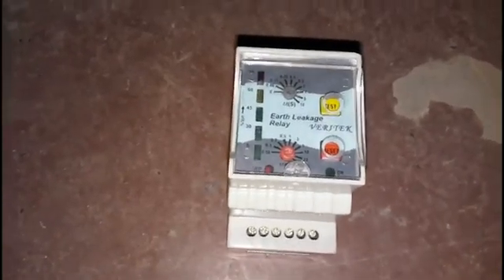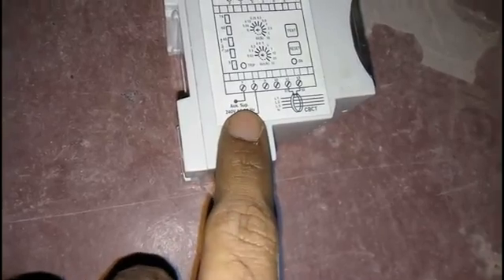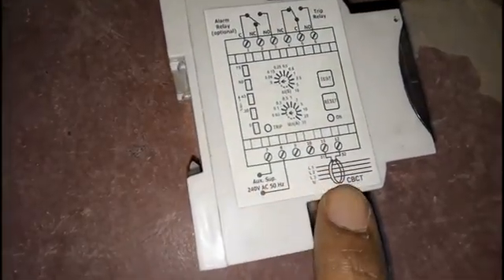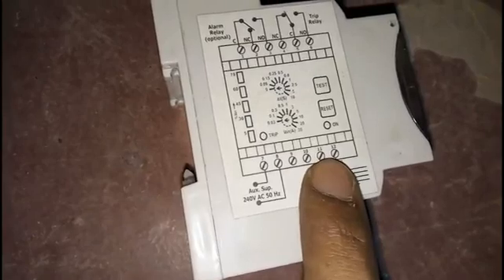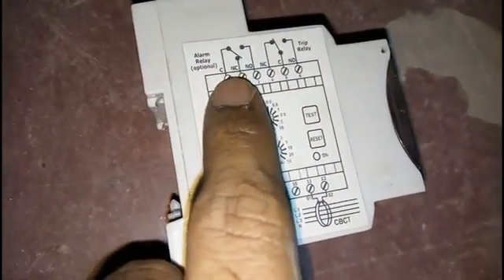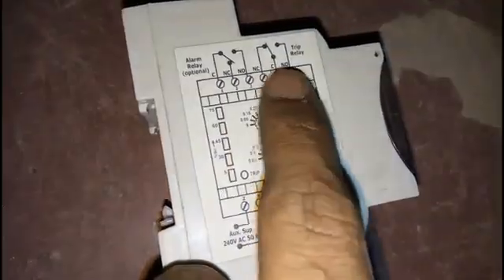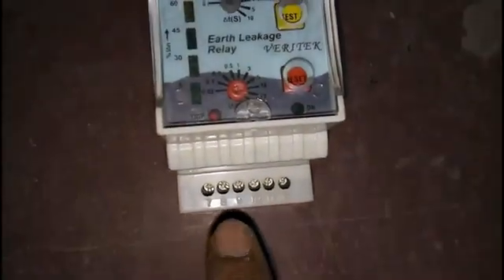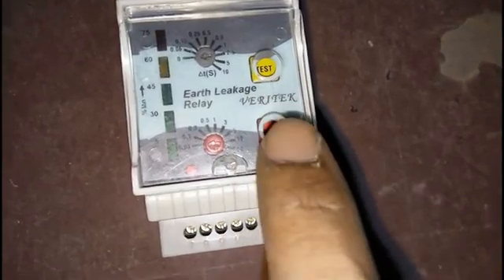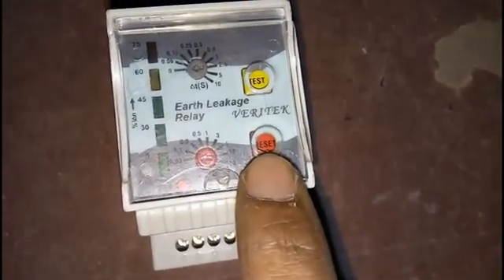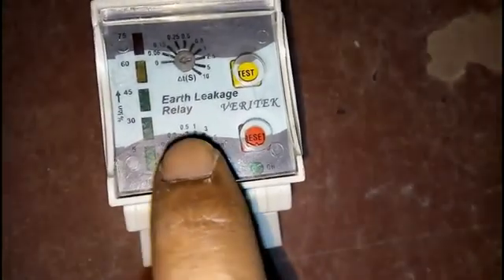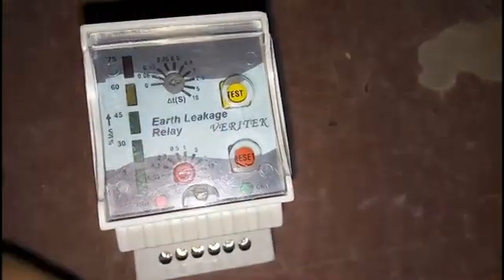This one is the ELR, and inside the ELR there is a wiring diagram. This one is auxiliary supply — 230 voltage AC supply. We have two types of relay: one is alarm relay and another one is tripping relay. Here we use the alarm relay only. The terminal number indications are available here. This one is the test button, this one is the reset button. Settings are available here for milliampere to ampere.